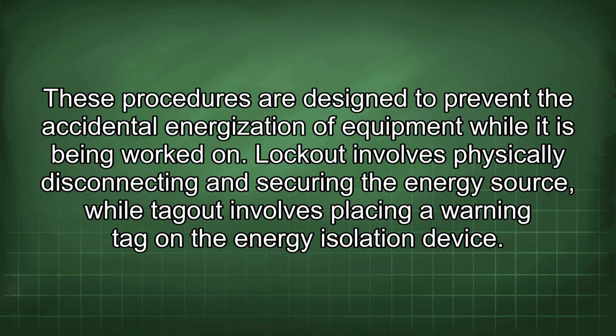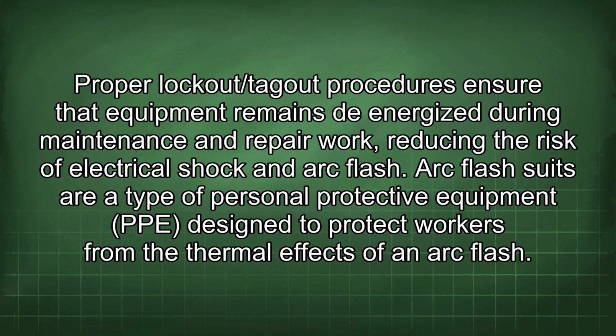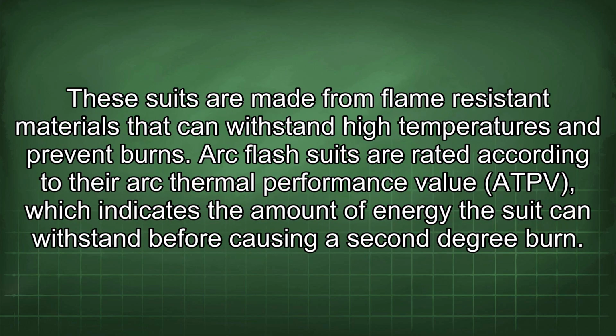Lockout involves physically disconnecting and securing the energy source, while tagout involves placing a warning tag on the energy isolation device. Proper lockout/tagout procedures ensure that equipment remains de-energized during maintenance and repair work, reducing the risk of electrical shock and arc flash. Arc flash suits are a type of personal protective equipment (PPE) designed to protect workers from the thermal effects of an arc flash. These suits are made from flame-resistant materials that can withstand high temperatures and prevent burns.